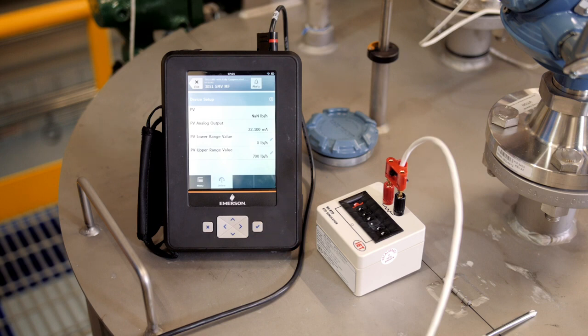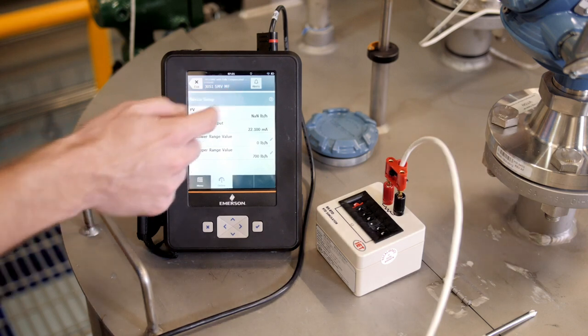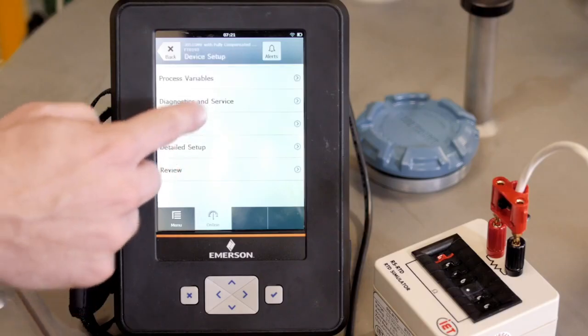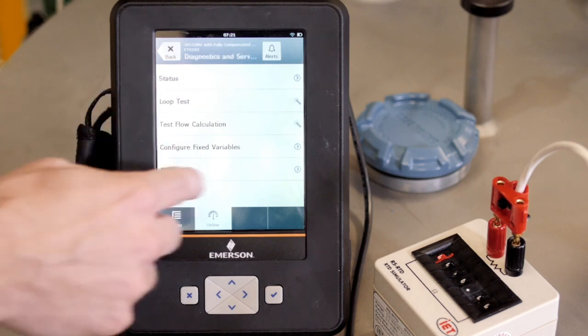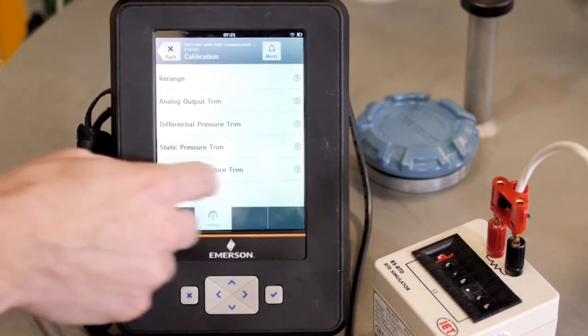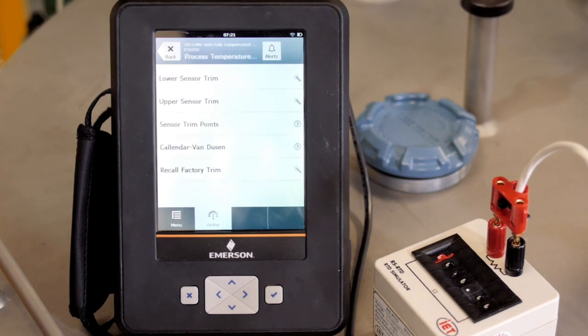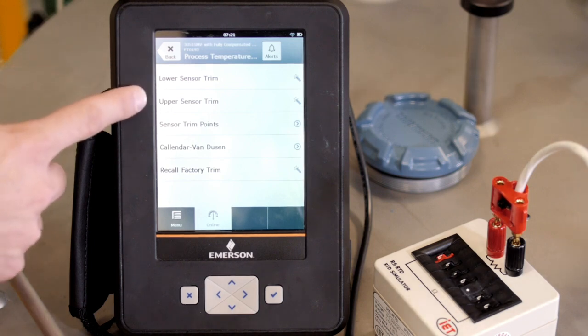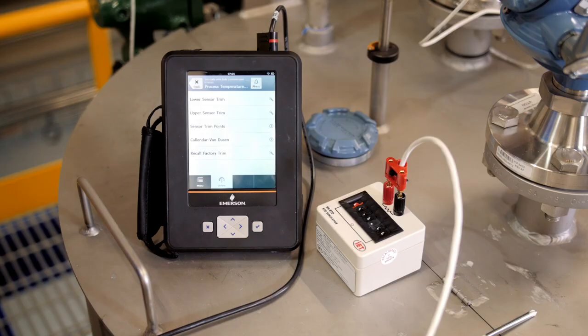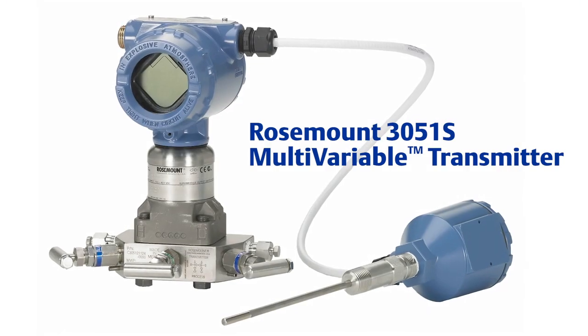Once again, go to the calibration page of the Trex and select the process temperature trim option. From here, we can follow the Trex guided wizards for the lower sensor trim and upper sensor trim options. Keep in mind, this process calibrates the temperature input on the transmitter and not the RTD itself. Once the lower and upper trims have been successfully performed, the calibration of all 3 sensors is complete.